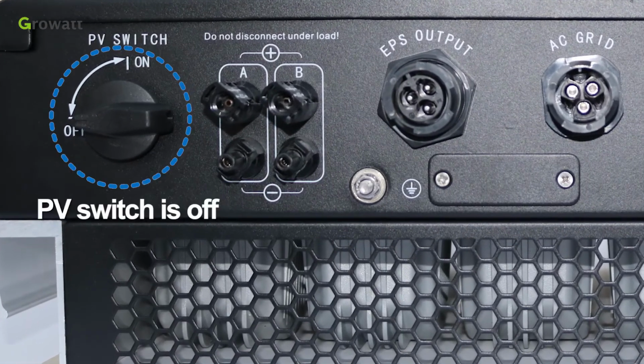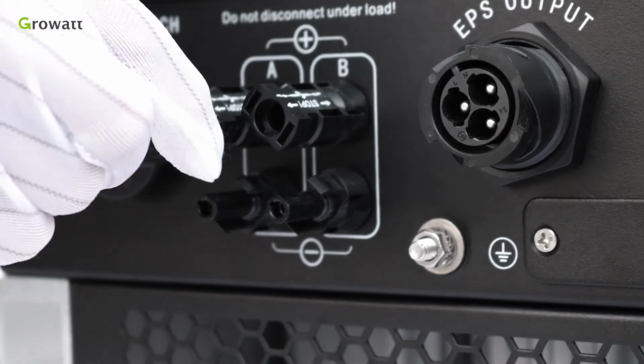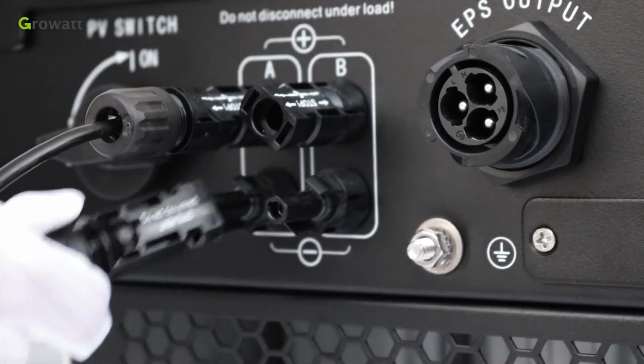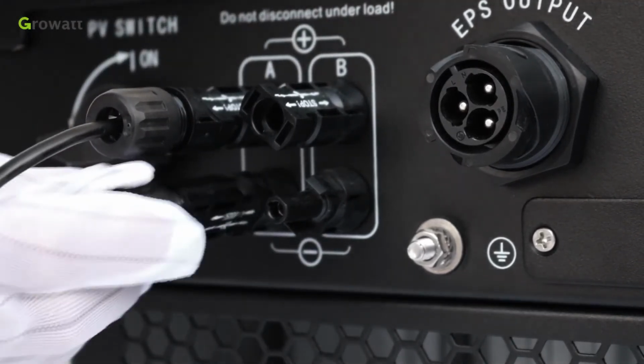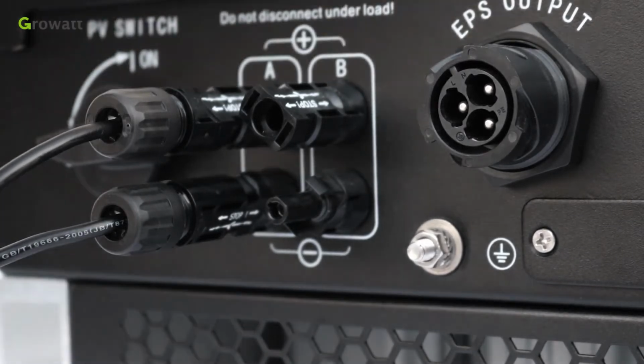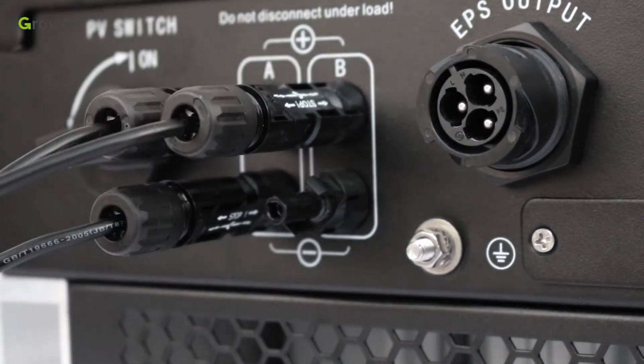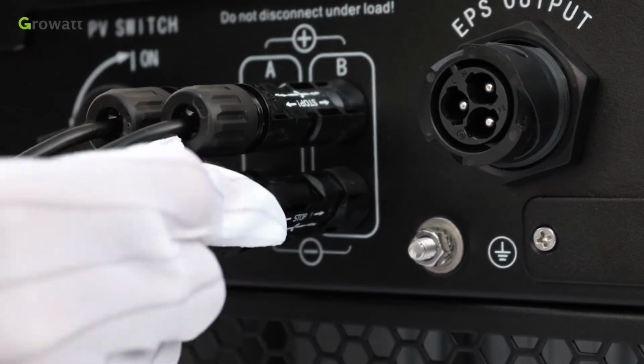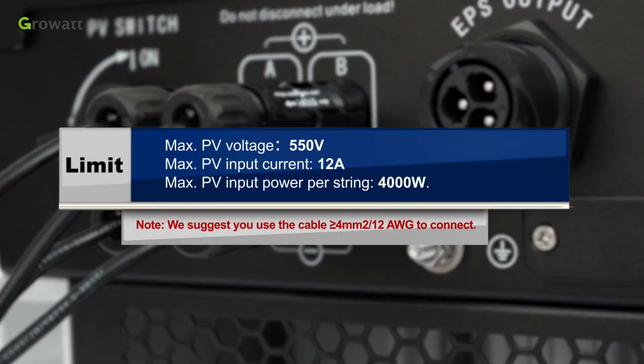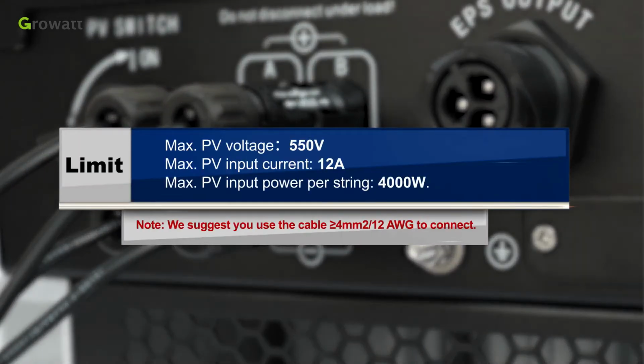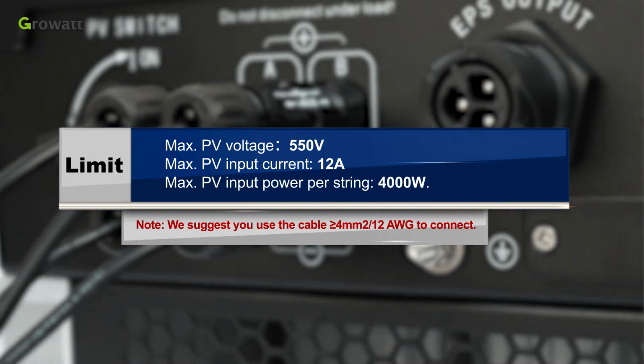One, make sure the PV switch is off. Two, similar to the traditional inverter connecting, the input of PV panel can be realized by using PV terminal. Three, insert positive and negative cables of solar panel into the relative PV terminal of SPH. Limit maximum PV voltage 550 volts, maximum PV input current 12 amperes, max PV input power per string 4000 watts. Note: we suggest you use a cable greater than 4 square millimeters, 12 AWG to connect.